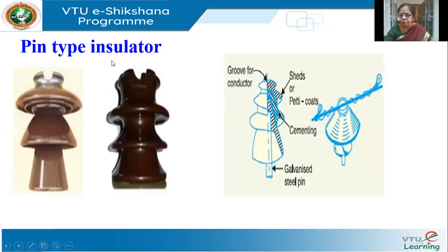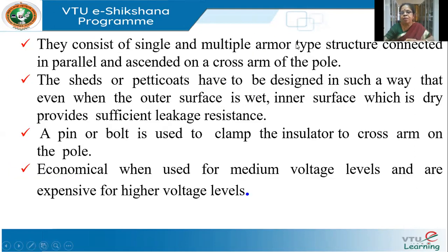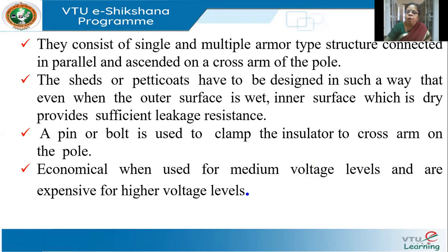When it rains, the water will fall on the insulator and slide off, keeping the inner surface dry even though the outer surface is wet. If everything gets wet, it may reduce the leakage resistance. So this design ensures that the leakage resistance is sufficient to prevent any leakage currents. It is called a pin type because there is a pin or bolt used to clamp the insulator to the cross arm of the pole.